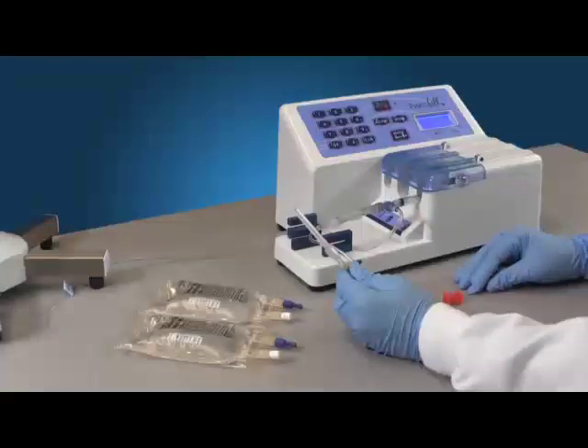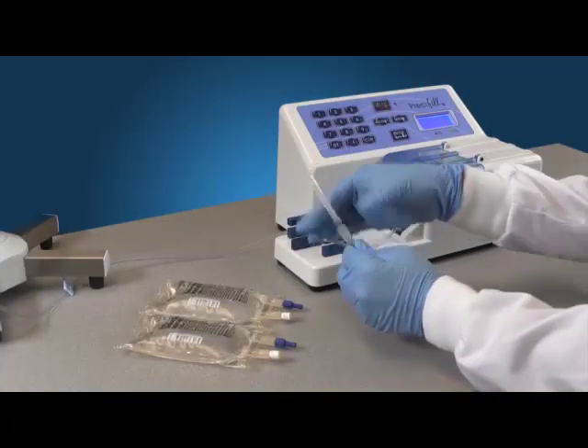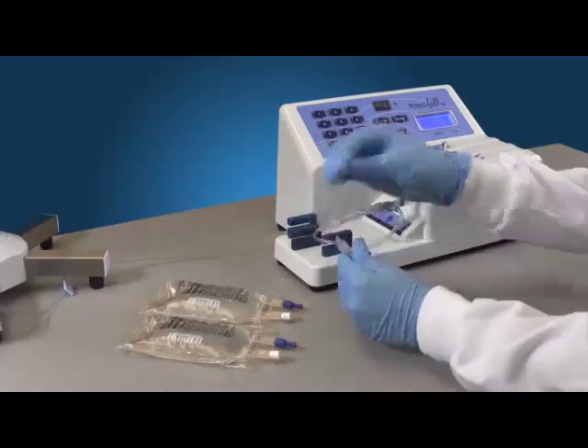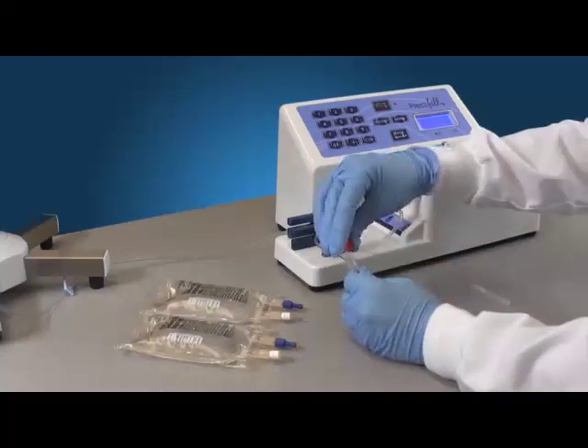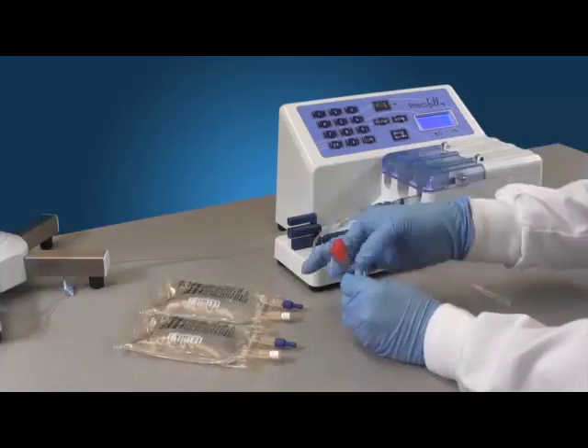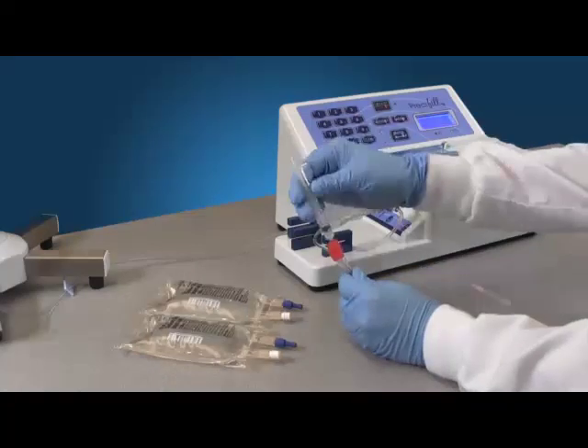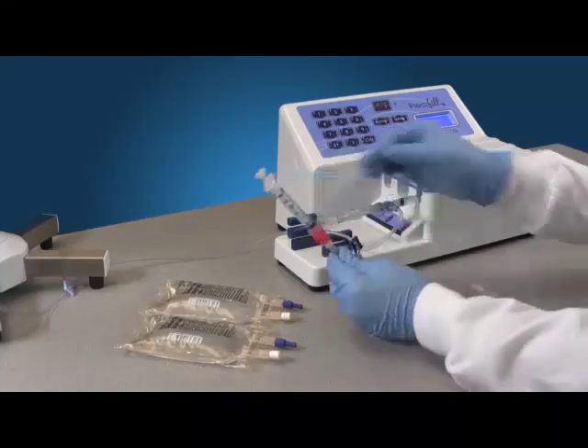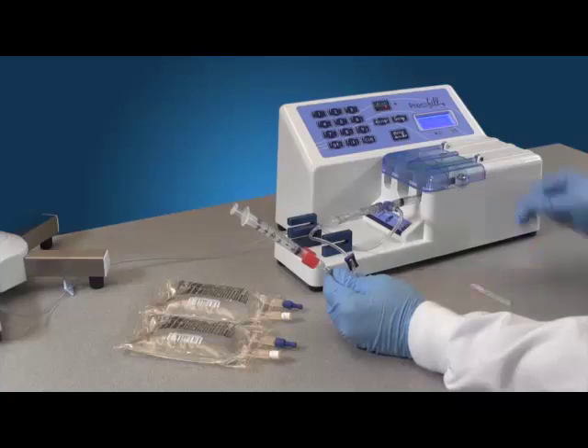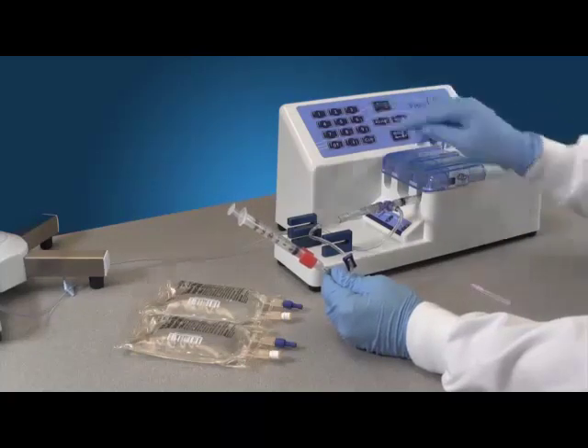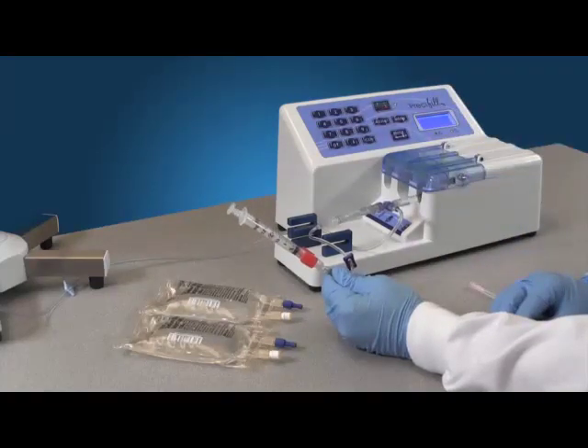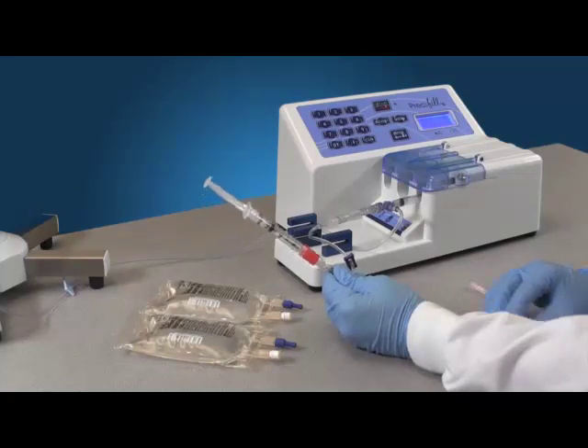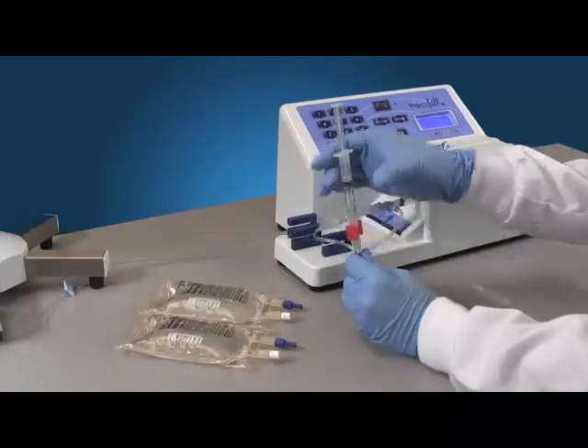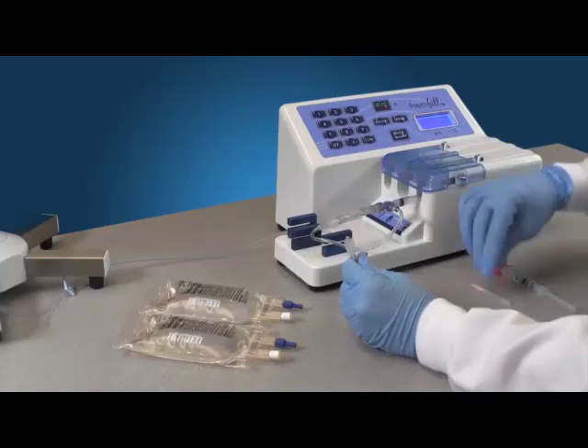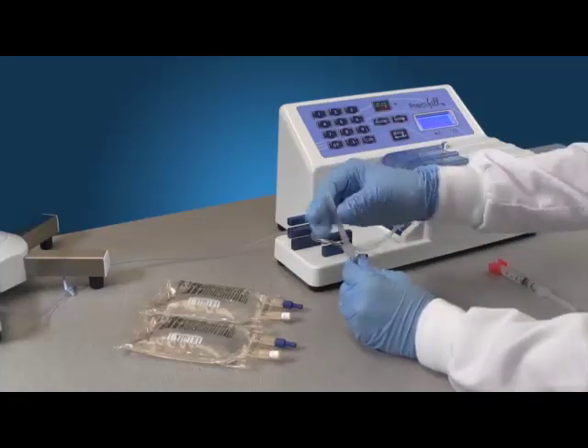To calibrate using the extension set, remove the needle after priming and attach the adapter. Attach a target syringe to the other end of the adapter. Hold the syringe to complete a fill to verify the volume. Adjust as needed. Once calibration is achieved, remove the adapter, attach a needle, and begin the filling process.